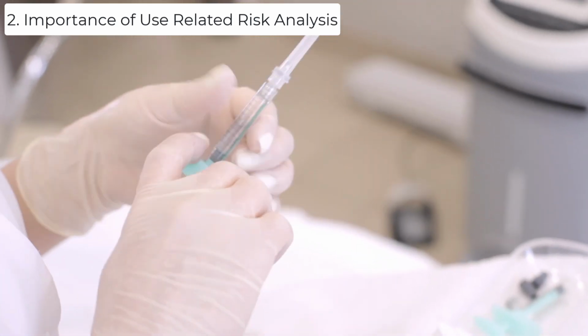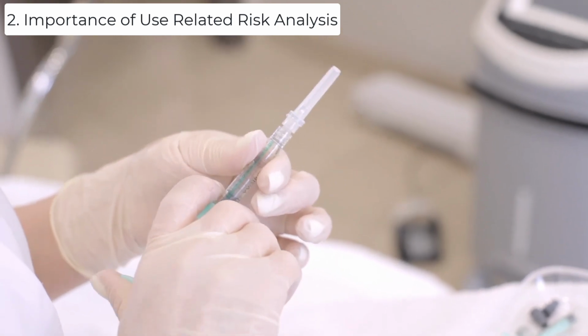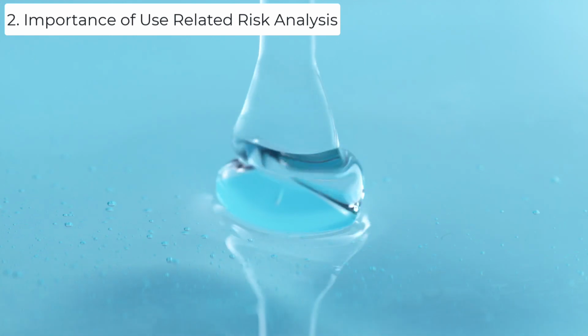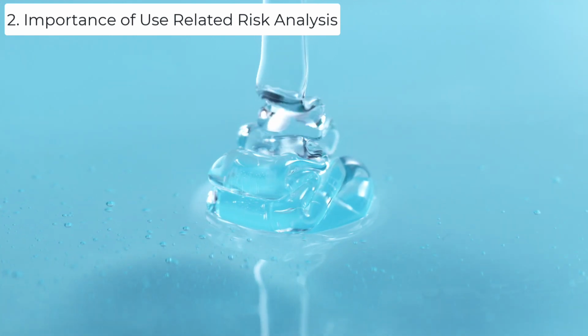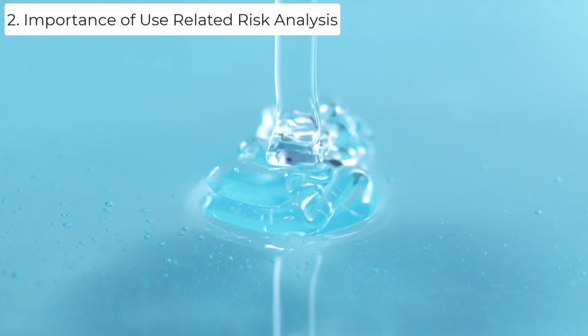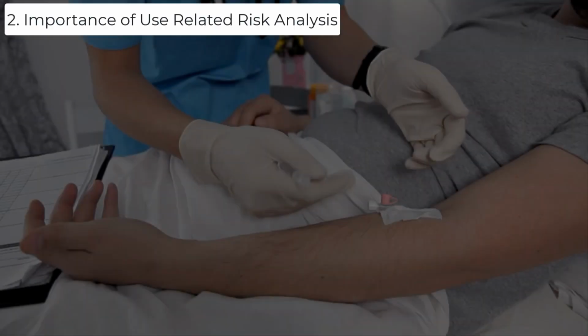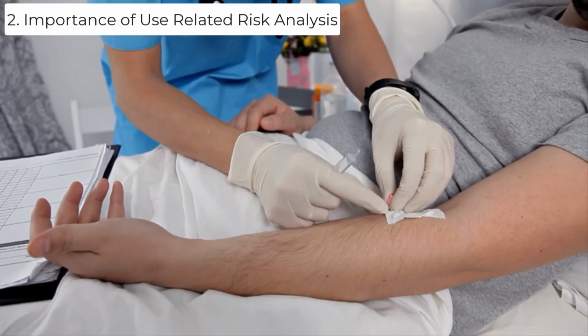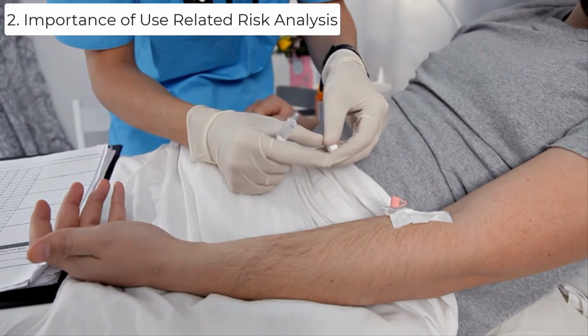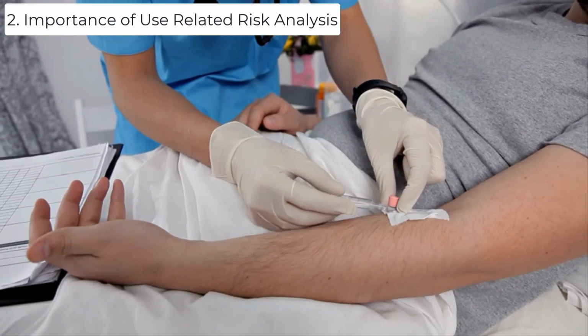For example, for a combination product like a medication injection device, a drug property like viscosity could increase injection delivery time and increase the risk of potential underdose. A use-related risk analysis should be conducted before beginning a clinical study, and that's to identify any potential risk of harm to the participants due to incorrect use of the combination product during the study.